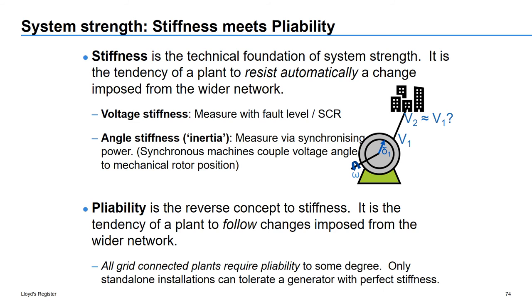Voltage stiffness or magnitude stiffness is really what we measure with fault level and short circuit ratio. In simple terms, it's really about how similar or different voltage magnitudes are between nearby points in a power system and how much this difference is sensitive to changes in the power flow. Angle stiffness is the equivalent tendency of voltage phase angles to move. In synchronous machines, angle stiffness is actually assured by physically coupling the angle of the internal EMF or voltage to the position of the rotor. This is quite important because the difference in phase angles is closely related in power systems to the real power flow or energy flow between two points. So it's quite an important concept.